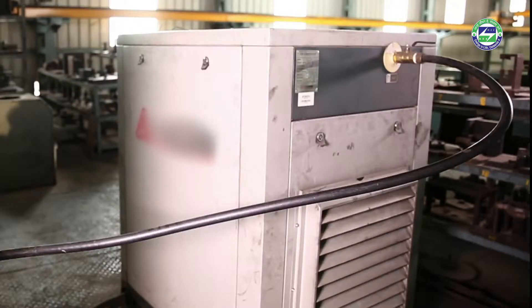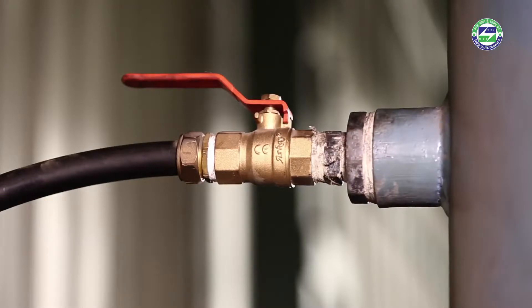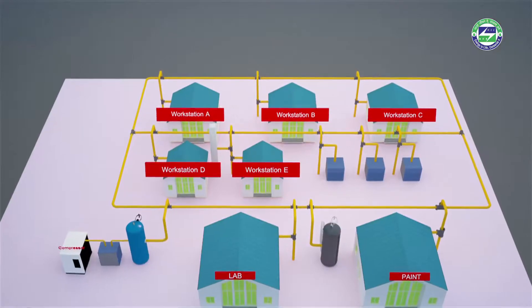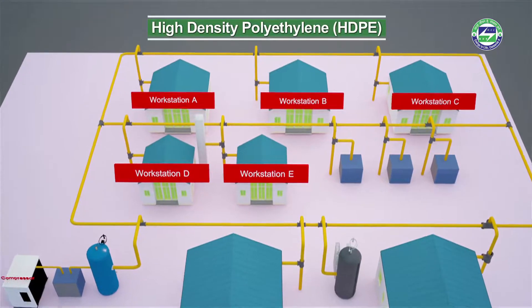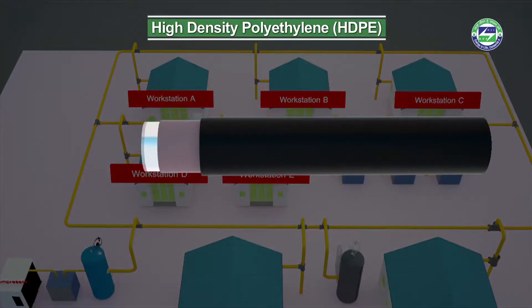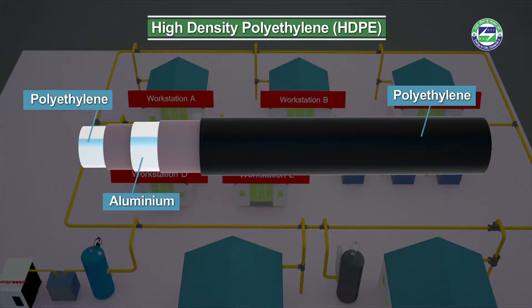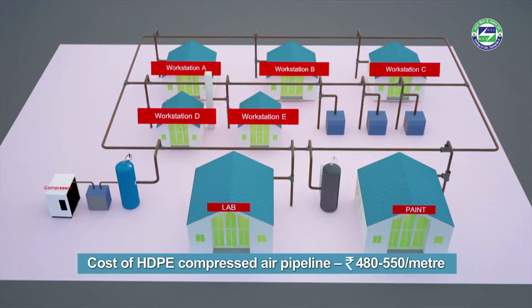In addition to piping network design, pipe material plays an important role in determining system efficiency. High-density polyethylene (HDPE) pipe is one such example increasingly used for efficient compressed air piping networks. An HDPE pipe consists of three layers: the innermost polyethylene layer, followed by a thin layer of aluminium, and an outer coating of polyethylene. The aluminium layer is bonded with the polyethylene layers using high quality adhesive.